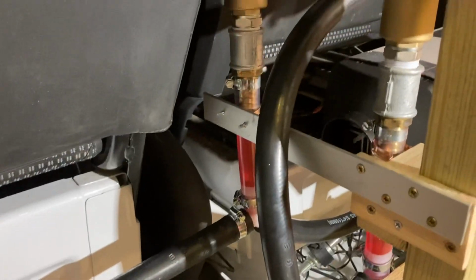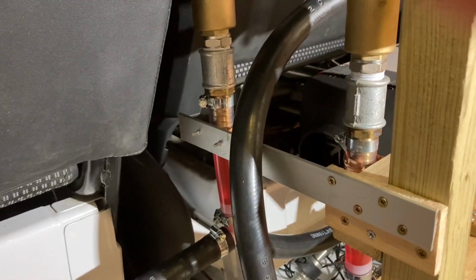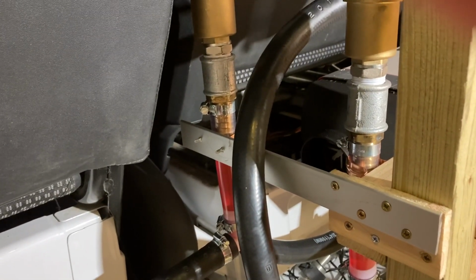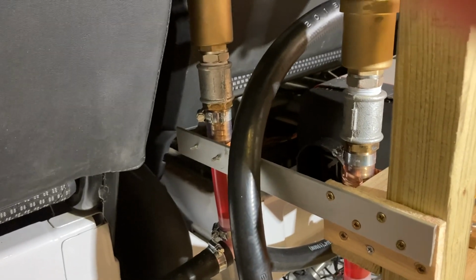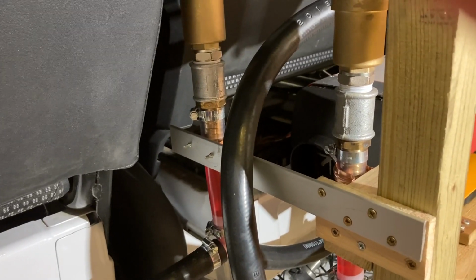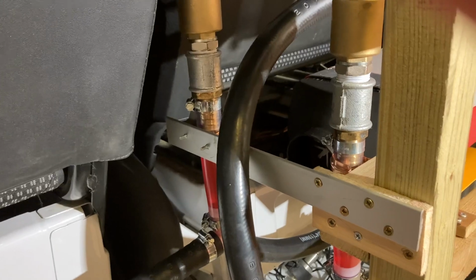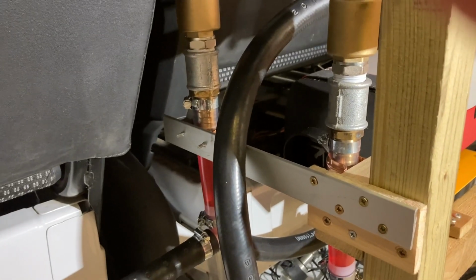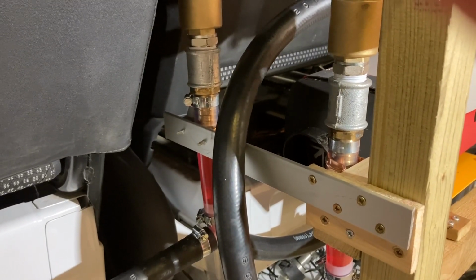One thing you do not want in this system is any gas or trapped air, because every time you turn it on it will build up, and you will end up with an airlock in your system whereby it won't run - or worse still, it will blow your pipes off if it starts to steam.